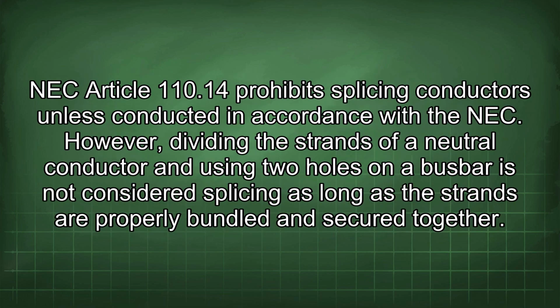NEC Article 110.14 prohibits splicing conductors unless conducted in accordance with the NEC. However, dividing the strands of a neutral conductor and using two holes on a busbar is not considered splicing as long as the strands are properly bundled and secured together.